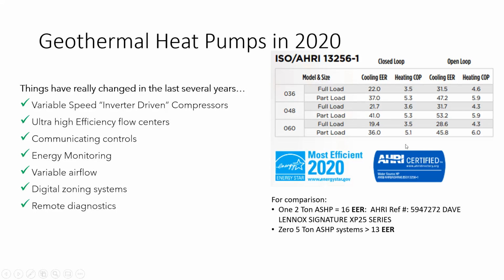If you look at typical closed loop performance, you can see the cooling EER, which let's talk about that in Texas. The EER of full load and part load averages out in the high 20s, mid 20s maybe, for a geothermal system between full load and part load. You look down here at the bottom, EER, not SEER, but EER, which is apples to apples. There's only one air source heat pump at 2 tons that even makes 16 EER, as compared to 25, all the way up to 53.2 EER with a geo unit. There are no 5-ton air source heat pumps in the world anywhere that achieve 13 EER.